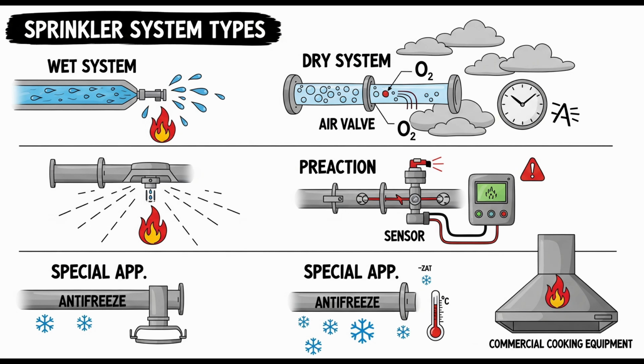What about right where the hood connects to the duct, the collar? A sprinkler or automatic spray nozzle is required at each hood exhaust duct collar. It must be located very precisely, between 1 inch minimum and 12 inches maximum vertically above the point where the duct collar connects into the hood plenum chamber. A very specific location window. Why there? That transition point is a prime area for grease buildup and potential fire ignition or spread into the duct. Placing a nozzle there targets this critical zone effectively.